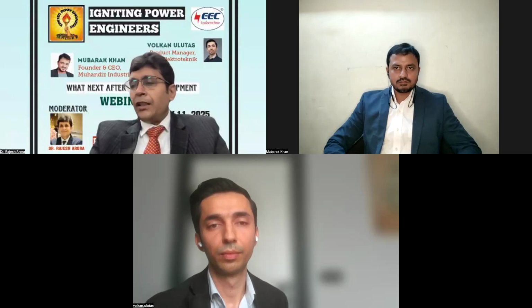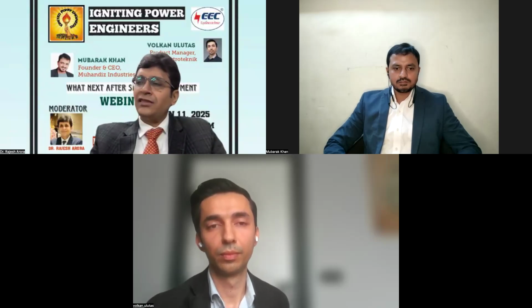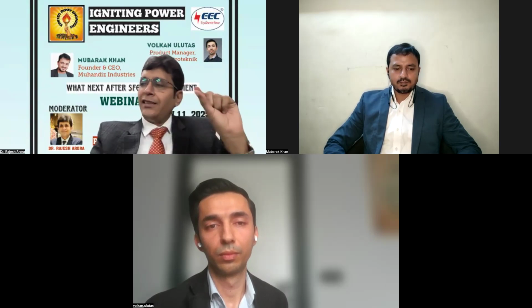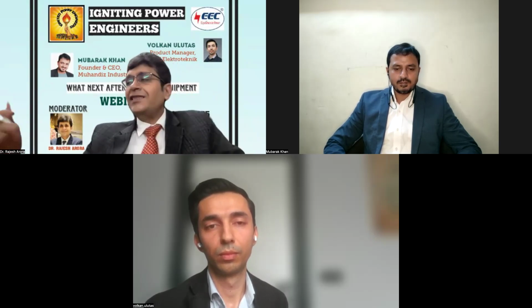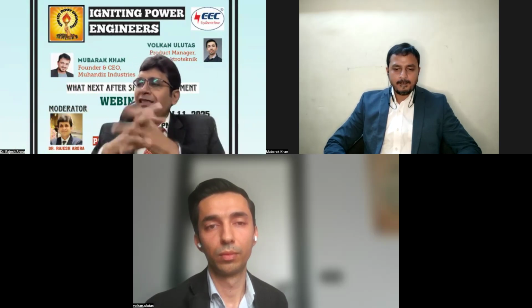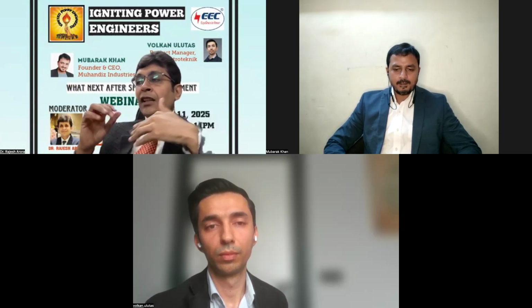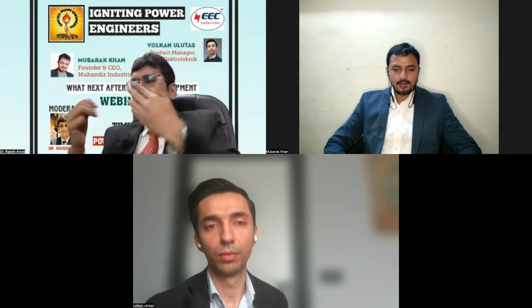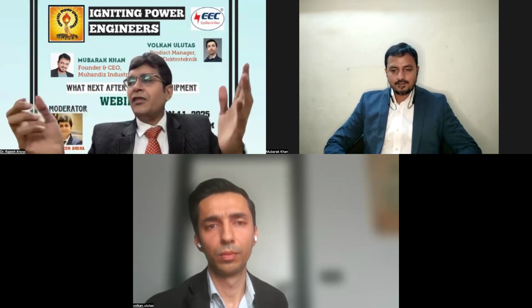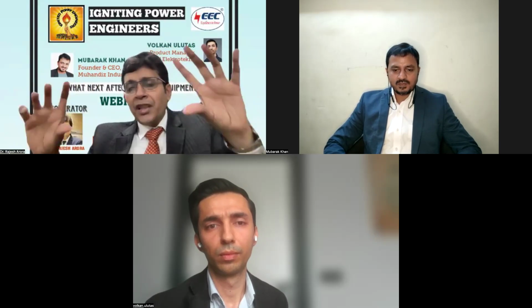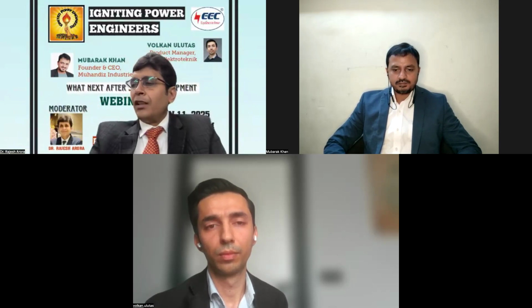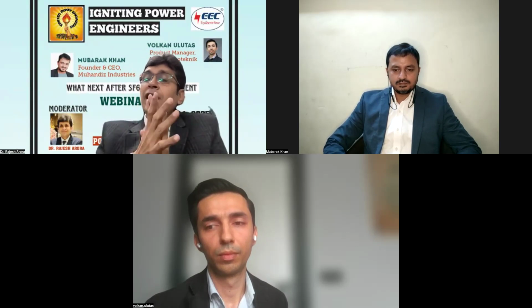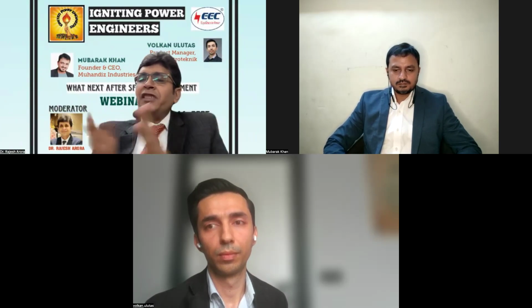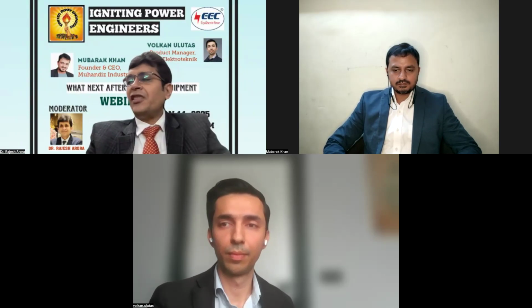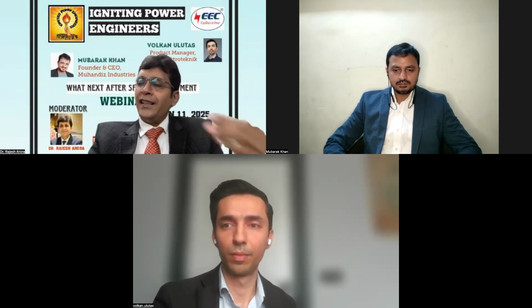Fifth reason, very important, is health and safety concerns. SF6 is non-toxic, but it can displace oxygen in confined spaces, creating a suffocation or asphyxiation risk if there is not large enough space relative to the leakage in that enclosed area. Apart from that, the byproducts of SF6 during very high arcing temperatures are not good for health.